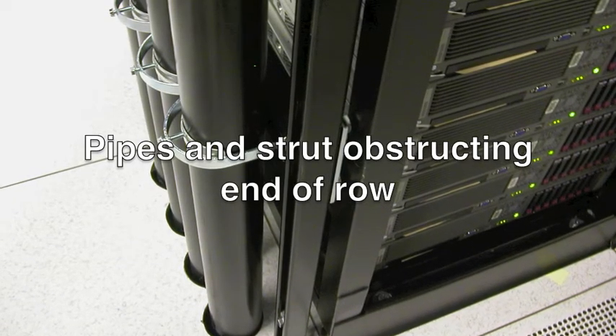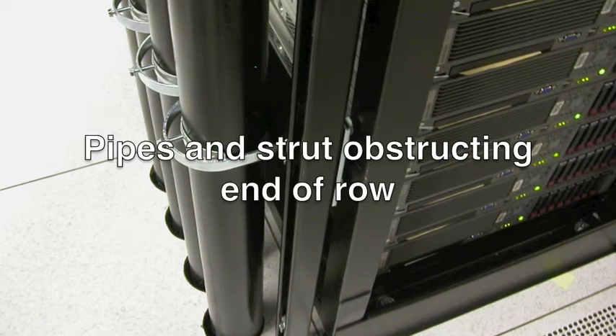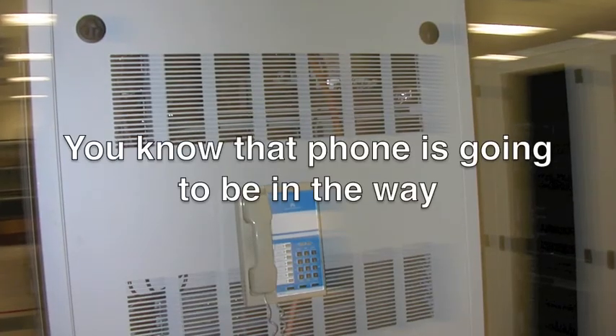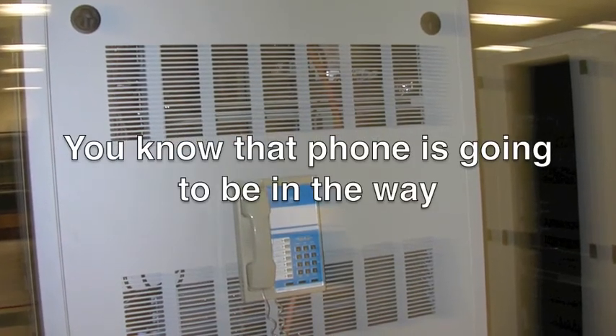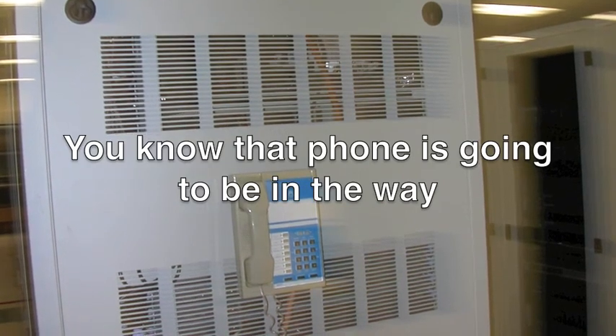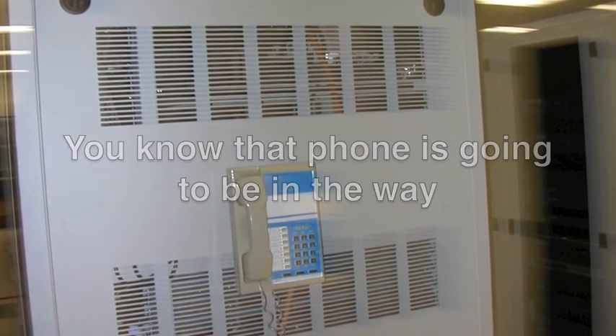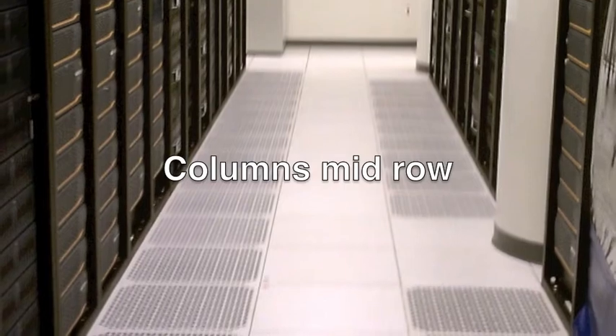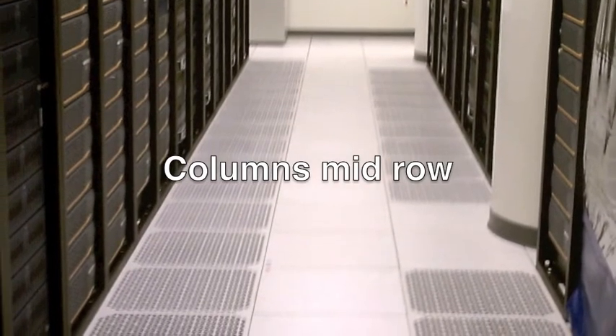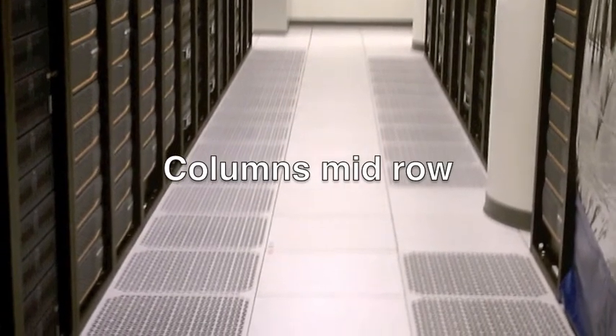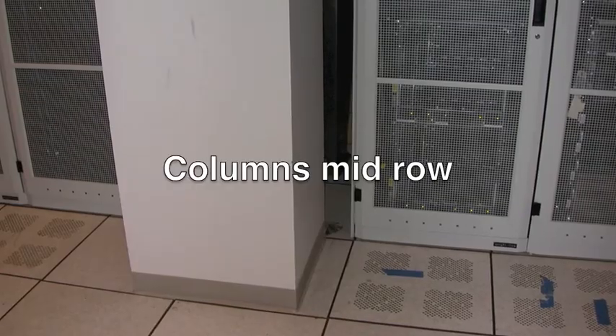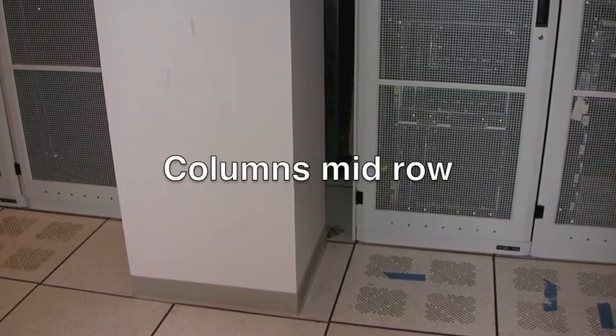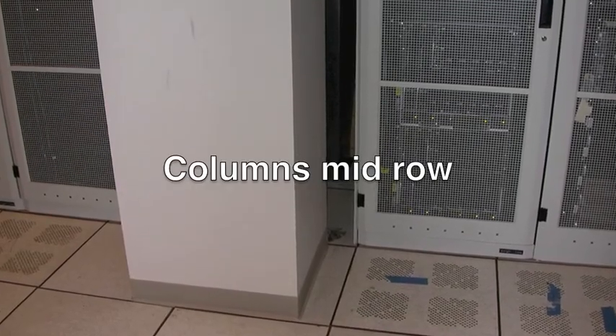Obstructions come in many varieties here. Pipes and strut at the end of the row obviously make installing a door difficult. The phone is indicative of things like fire extinguishers and first aid kits that we often run into. And then columns, typically somewhere in the row like these two examples here. So if you're putting a roof across there, that becomes difficult, and then the gaps between the columns and the racks need to be accommodated.